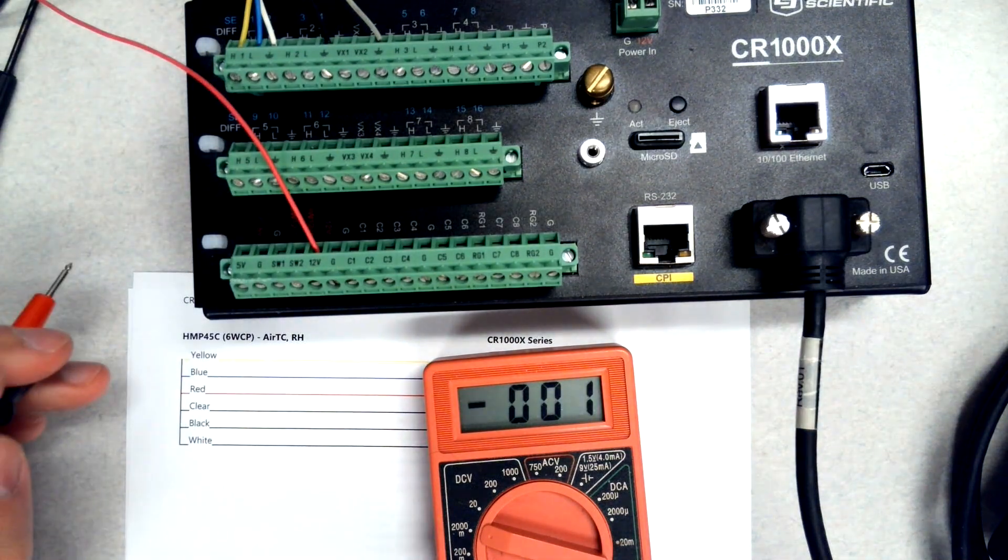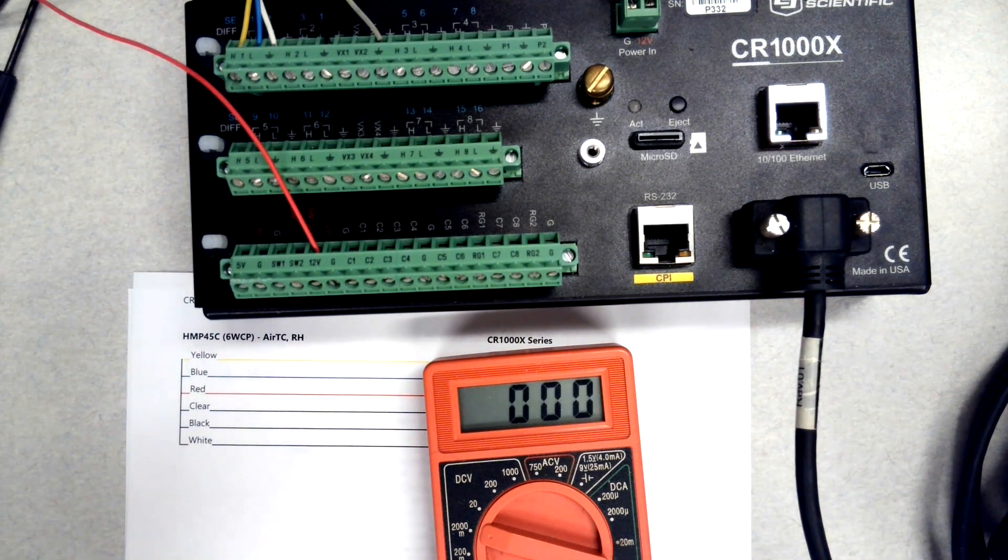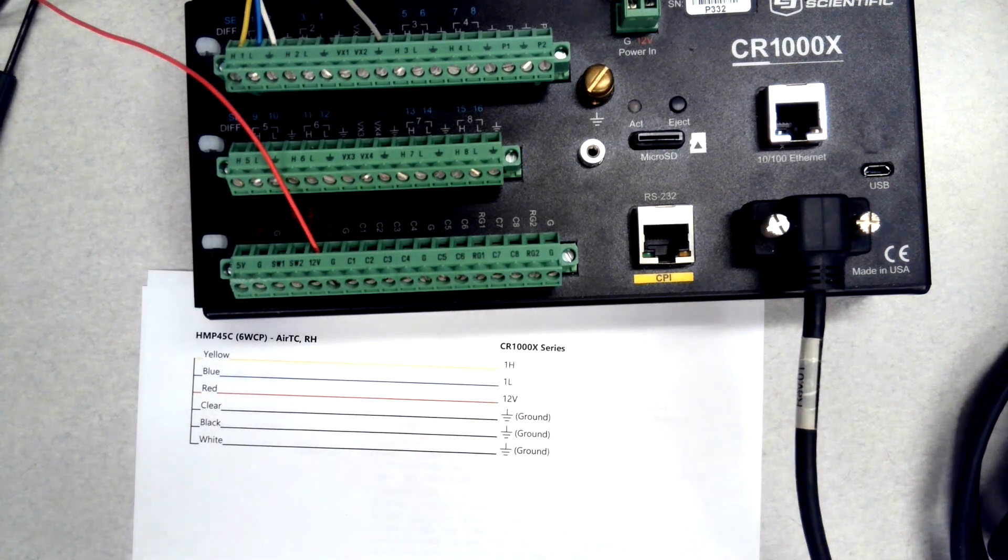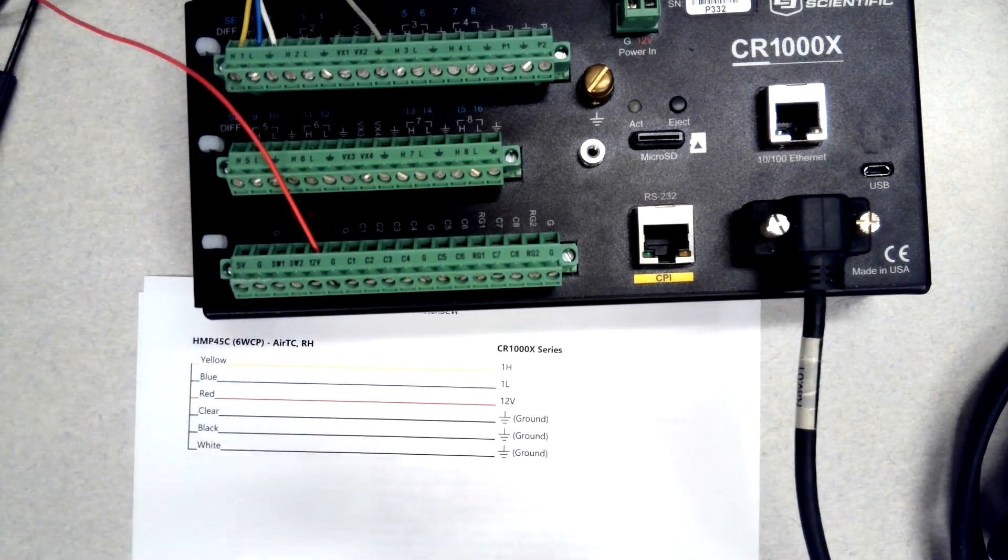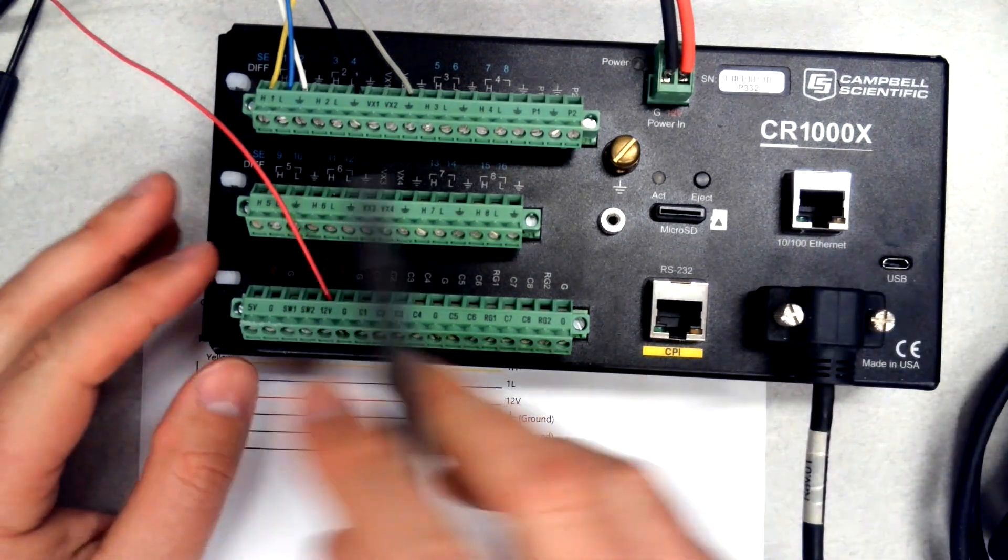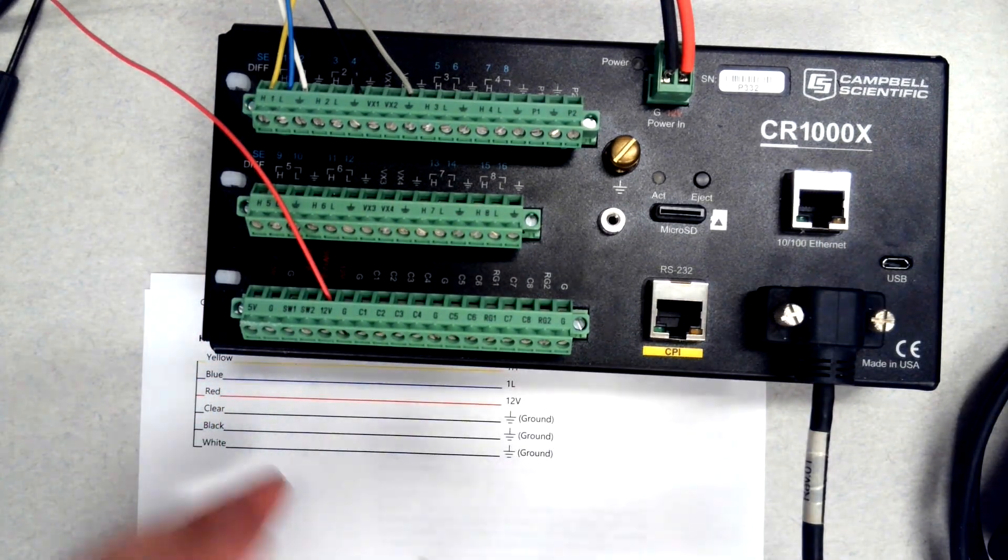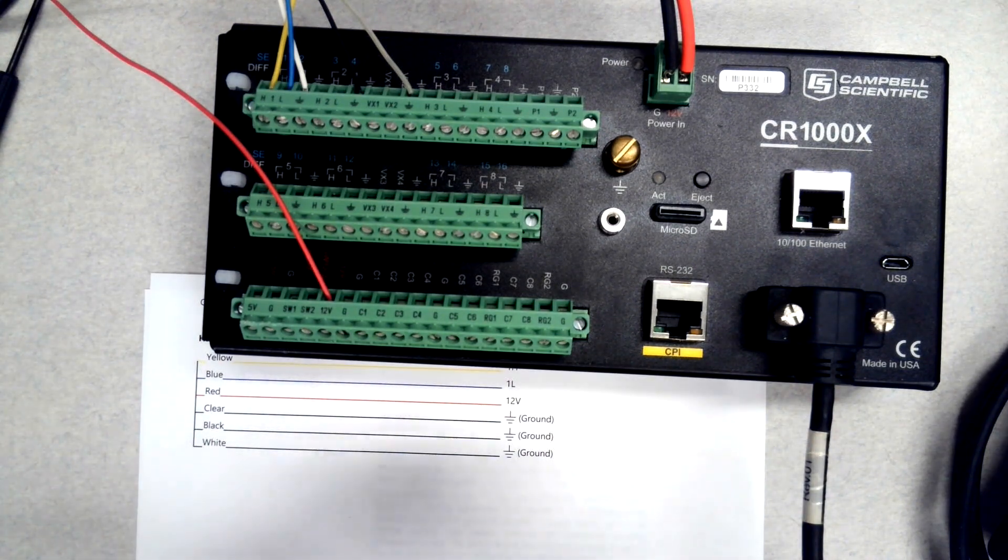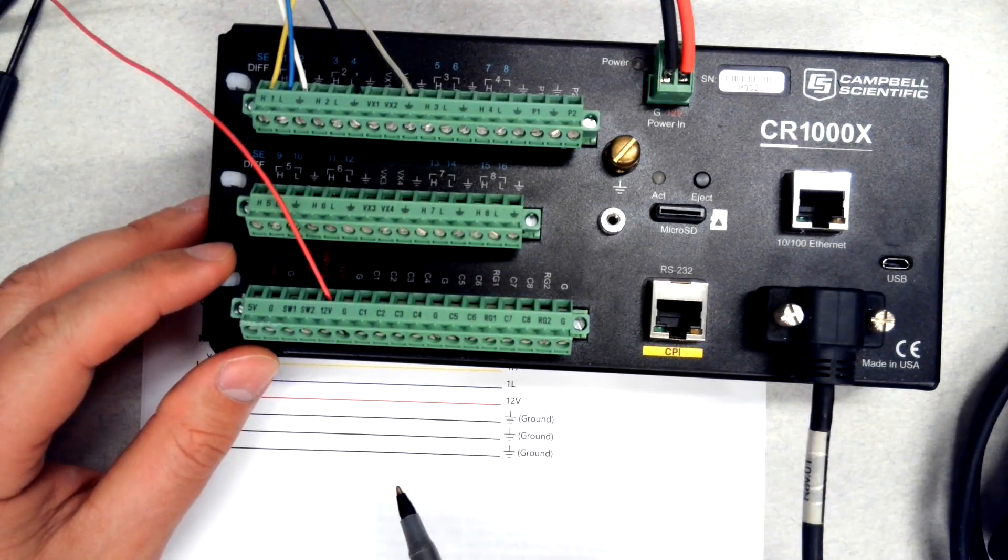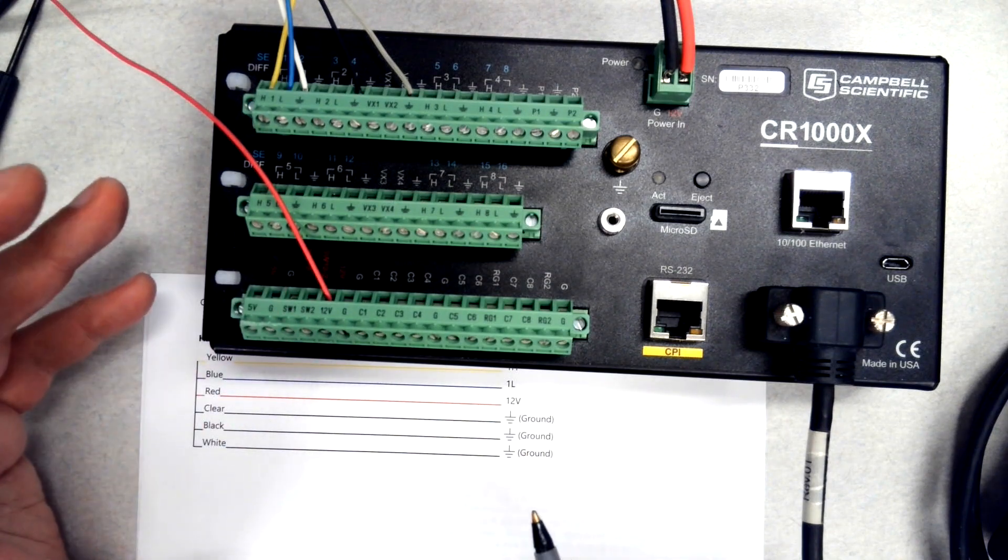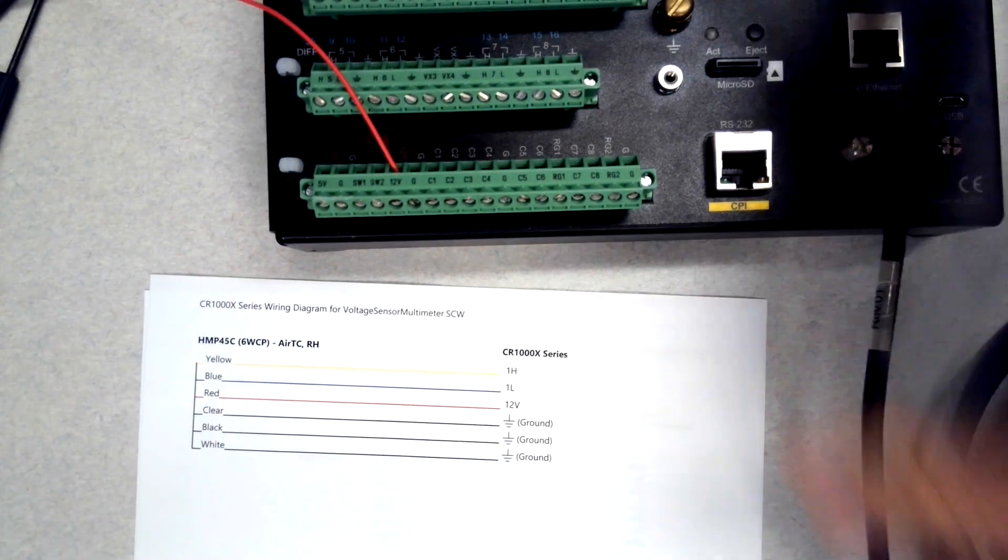According to my display, that is 17.8 on the humidity. Now at that point you're done taking your measurements, but you then have to do some math. The nice thing about voltage output sensors is I did not have to disconnect anything and it did not interrupt the data logger's measurements. With voltage output sensors, just leave them connected, but you need to know which wires are which, particularly since the sensor needs power.